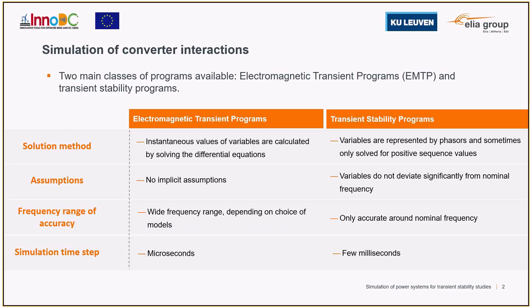Due to the high level of detail of EMTP models and the small time steps used, simulations tend to be slower, while in transient stability programs the lower level of modeling detail allows for faster simulations and larger time steps.